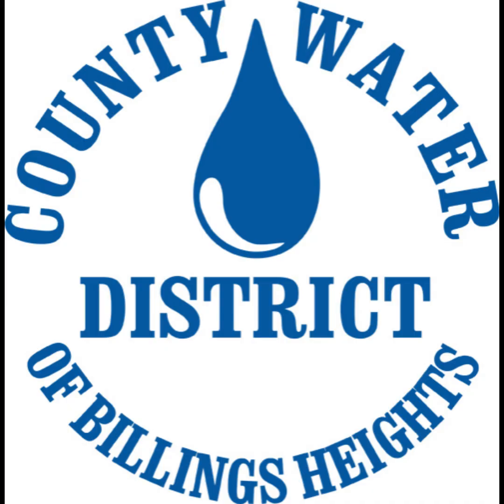Right, I mean, testing, it's one of the most accurate, but the problem is, if you use probably a standard differential pressure transducer, if they're not calibrated and adjusted properly to the sweet spot of the Venturi, you've got a big problem. Well, I think I understand that's the problem. So, you can adjust that pressure differential transducer outside in the lab, okay? Yeah. And I would send it to those people in Rhode Island and have it tested.